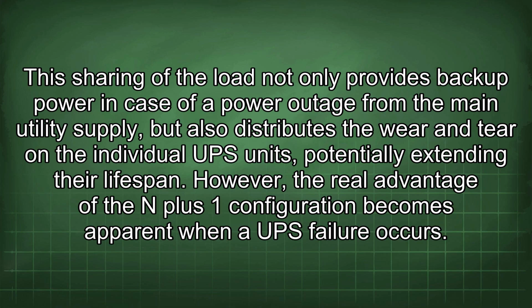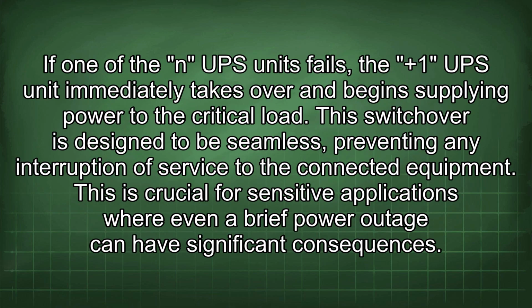This sharing of the load not only provides backup power in case of a power outage from the main utility supply, but also distributes the wear and tear on the individual UPS units, potentially extending their lifespan. However, the real advantage of the N+1 configuration becomes apparent when a UPS failure occurs. If one of the N UPS units fails, the +1 UPS unit immediately takes over and begins supplying power to the critical load. This switchover is designed to be seamless, preventing any interruption of service to the connected equipment. This is crucial for sensitive applications where even a brief power outage can have significant consequences.